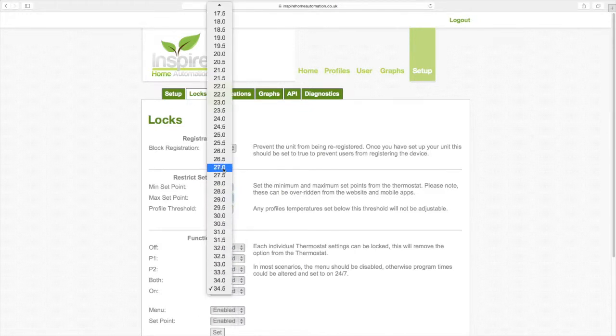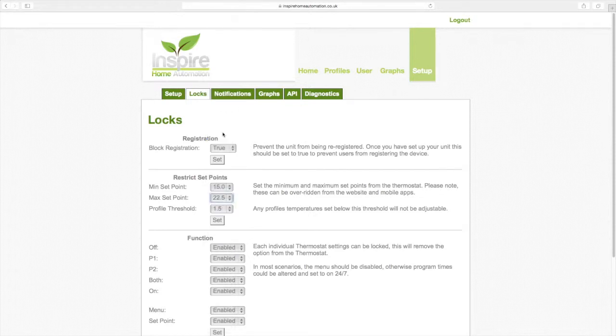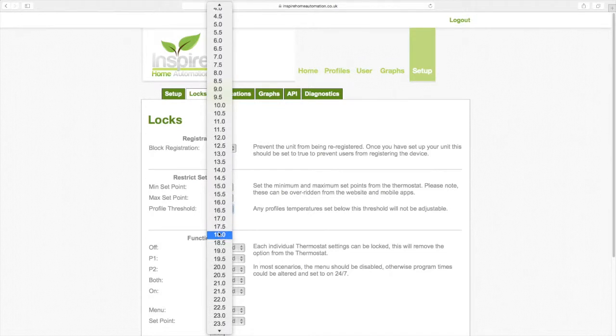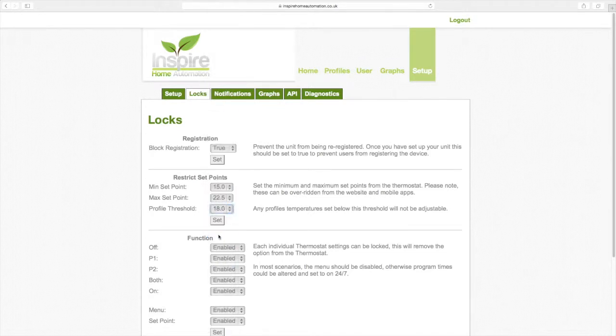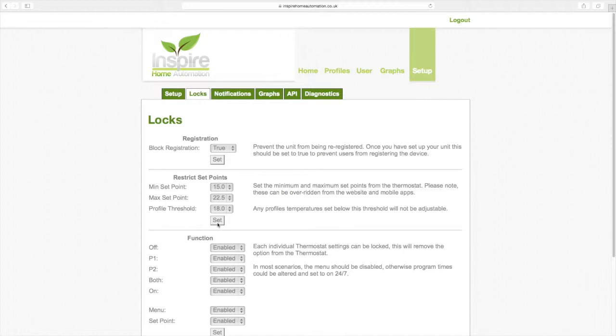We are also going to set a profile threshold of 18 degrees. The profile threshold is only available when using profiles. Any profile segment below this temperature is locked. So in this example, any profile segment set to below 18 degrees cannot be adjusted. Any segments above 18 degrees can be adjusted between 15 and 22.5 degrees.